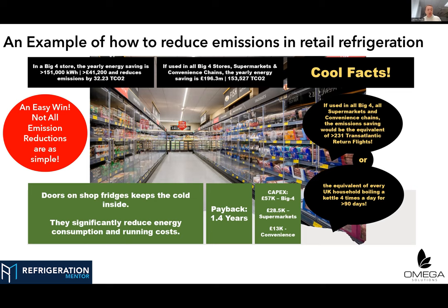So what I've done here is a piece of work looking at the big four supermarkets in the UK — Tesco, Sainsbury's, Asda, and Morrisons. The yearly energy saving if they put doors on all their chilled display cases is 151,000 kilowatt hours per store. This is over £41,000 and it reduces emissions by 32.23 tons of CO2 per year.